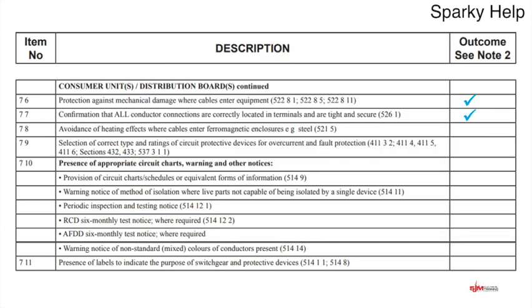The only one that doesn't need to go through is the earth, but all the live conductors must all go through the same hole. Or you can change the gland plate to Paxolin, but then you just cut a slot anyway, or something non-magnetic. So hopefully that will be a tick, because all your single conductors have gone through the same enclosure, same hole.